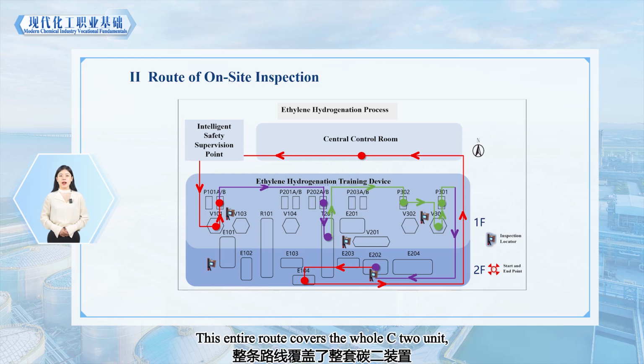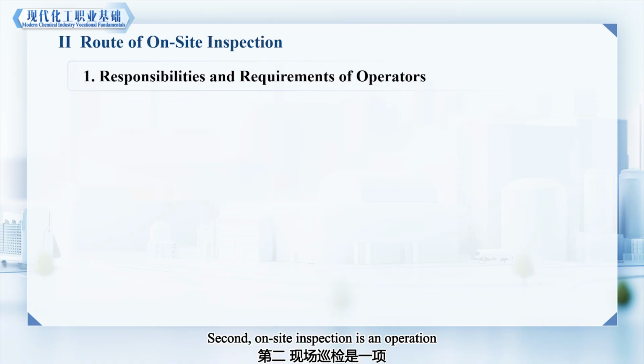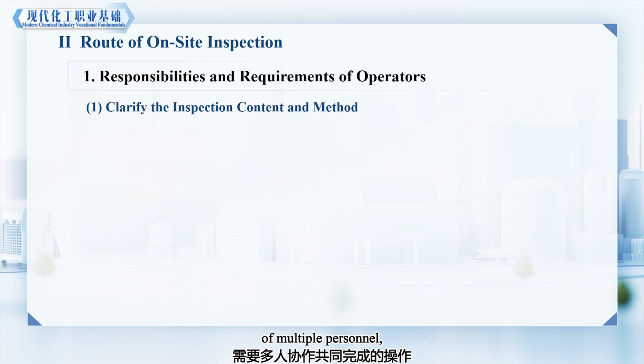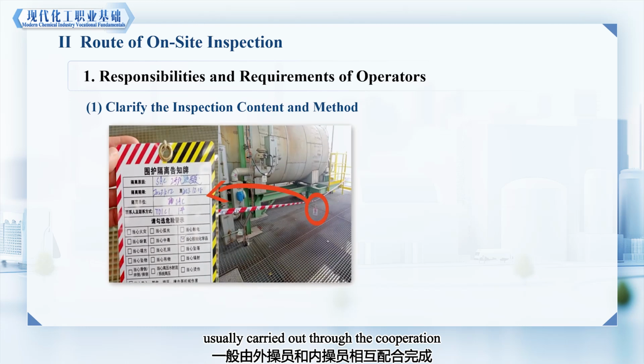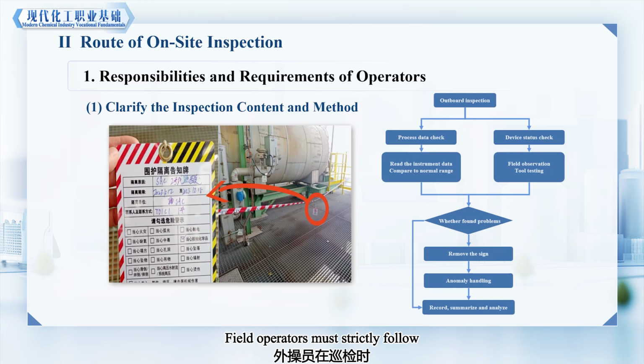This entire route covers the whole C2 unit, effectively ensuring the unit's stable operation. Second, on-site inspection is an operation that requires the collaboration of multiple personnel, usually carried out through the cooperation of field operators and control room operators. Field operators must strictly follow the inspection checklist when inspecting, and if any abnormalities are found, they must report them immediately and isolate the unit with warning tape and display a maintenance isolation notice.